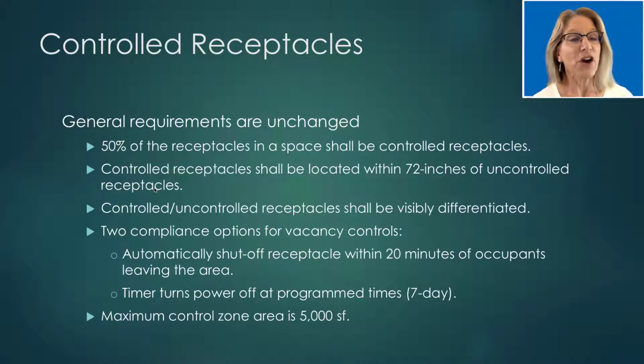And then there are two compliance options for how the vacancy controls can be handled. They can be set up so they automatically shut off the receptacles within 20 minutes of occupants leaving the area, or they can be controlled via a timer switch, which turns the power off at programmed times. And if that is the approach taken, then the programmability of that system needs to be 7-day standard programmability. And then the maximum control zone area for controlled receptacles is 5,000 square feet.